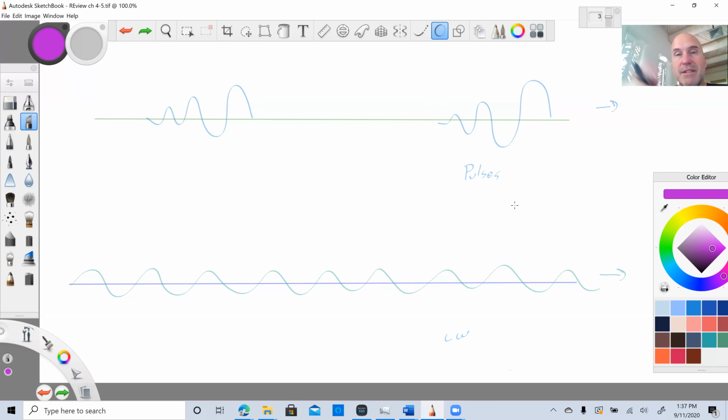Very shallow imaging, listening time is very short. By the way, that creates a more pleasant experience when you're watching the screen. You move the transducer and everything is instantaneous because there's very little listening time. When you're very deep and you have to listen, you cannot send out another pulse until all the echoes come back. You move your transducer fast, there's a lag on the screen. It's not pleasant to look at.